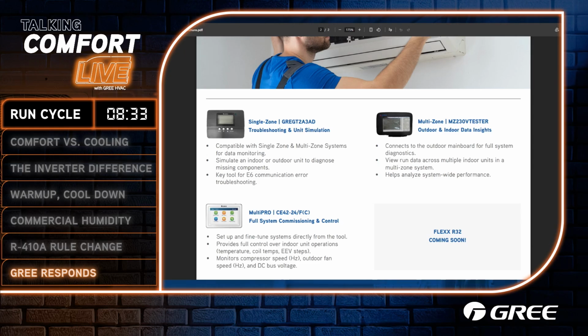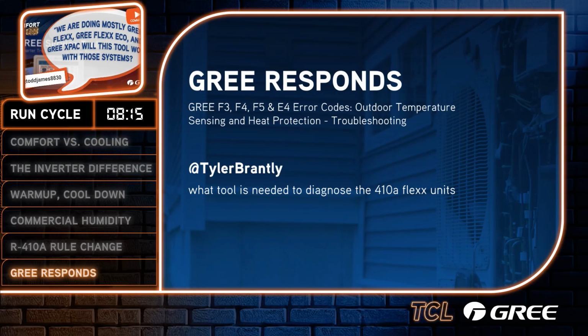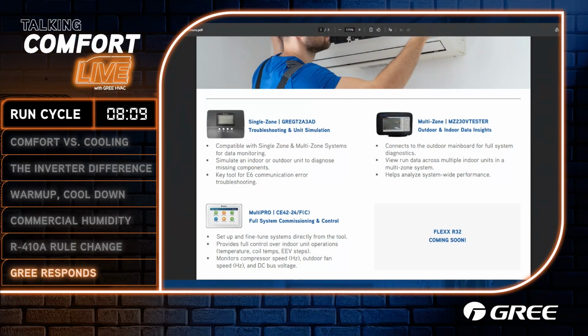And I even have some videos on our website too that show me troubleshooting an E6 code with the single zone tester, and you can read the indoor sensors, the outdoor sensors, the EV steps, the hertz of the compressor. So there's so much information that these tools actually give you. And again, like I say, reading all the sensors, sometimes, if you have one zone that's acting up, you can get in there and check the sensors to that zone. A lot of times that's why it's not feeding properly.